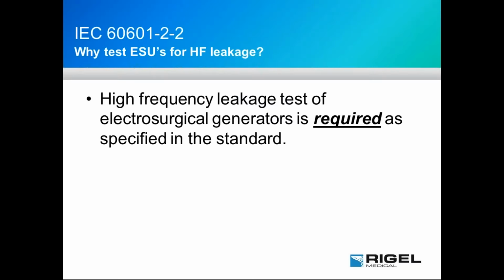And here it's under 60601-2-2. For leakage current, the big thing is it should not exceed 150 mA. That's what you're basically looking for. This is documentation of how a manufacturer will set up and test for high frequency leakage. They'll have different points that represent the body, and you can see the 200 ohm resistance measuring the high frequency meter and then different points throughout the table. This is what the manufacturer will use. And if you've been to some schools, you actually see the setup of this.